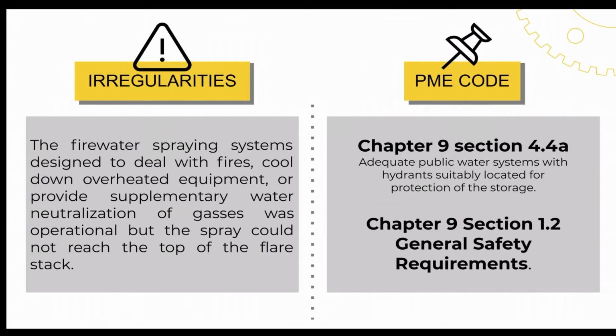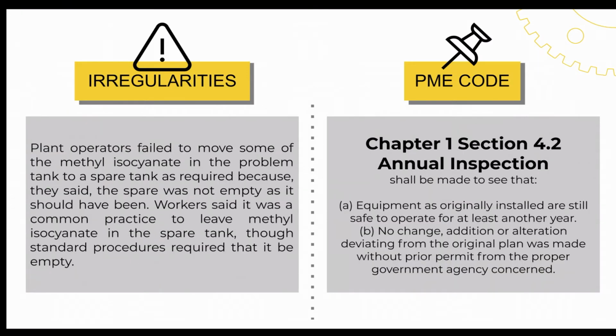Another irregularity found was the firewater spraying system, designed to deal with fires, cool down overheated equipment, or provide supplementary water neutralization of gases. It was operational, but the spray could not reach the top of the flare stack. This violated PME Code Chapter 9, Section 4.4a, adequate public water systems with hydrants suitably located for protection of the storage. This also violated Chapter 9, Section 1.2 of General Safety Requirements, which states that the facility shall install, provide, incorporate, adapt, and maintain under operable and usable conditions the automatic fire protection devices, equipment, fire safety construction, and warning system.